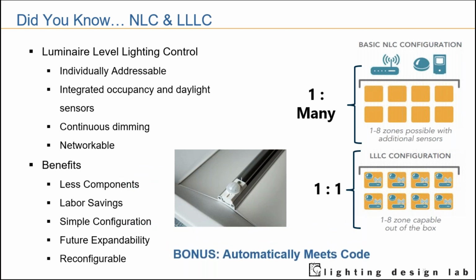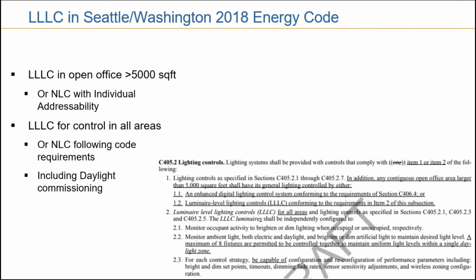And as an added bonus, depending on where you're at, because we're here in Seattle, Washington, these automatically meet code. What do I mean by that? It's actually written starting in the 2018 Seattle, Washington energy codes that if you have an open office that's 5,000 square feet or greater, you're going to require luminaire level lighting controls or an NLC system with individual addressability, at which point, hey, might as well go for the LLLC system. Also, when it comes to section C405 for lighting controls, if you have luminaire level lighting controls in all areas, in terms of meeting code, all you have to do is a quick check mark on your commissioning or your code packet and keep it going.